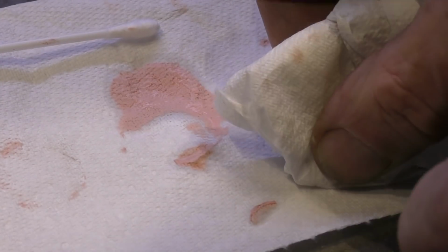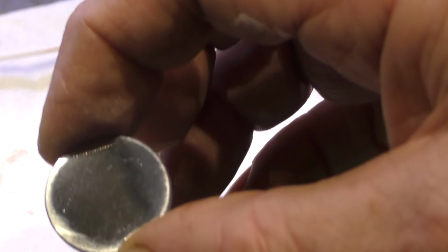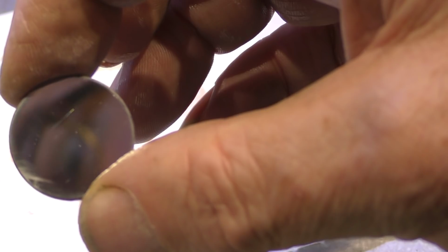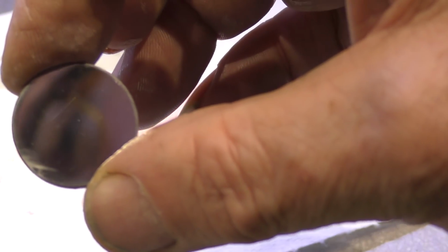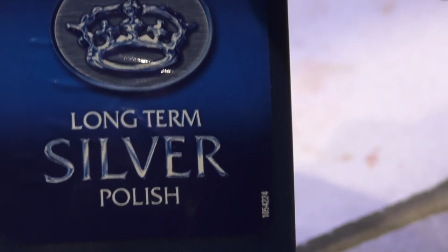We'll just give it a quick final wipe with soft tissue. As I said, because this is molybdenum, you can be quite aggressive with it. And hey, here's looking at you, sunshine. Now remember what I said, the only mirrors you can attempt this with are molybdenum mirrors. So whichever method you choose to use, before you start your beam alignment, go around and clean all your mirrors.